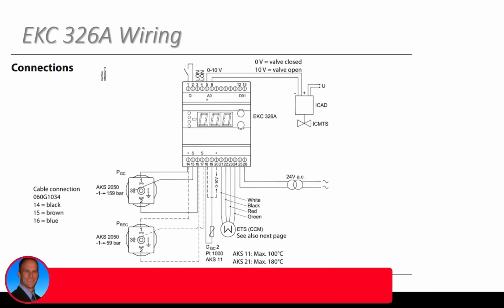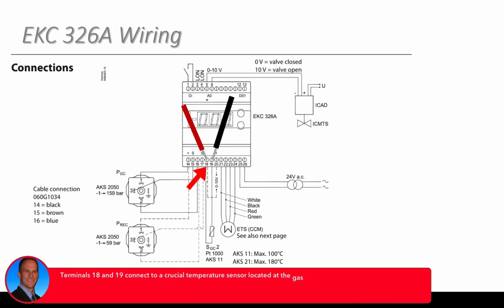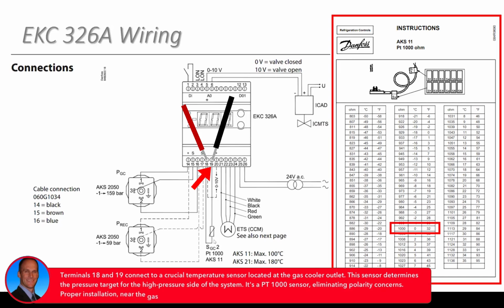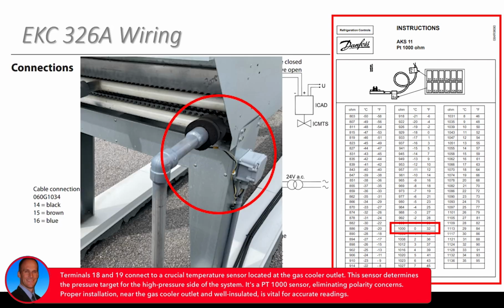Yeah, awesome. And then we've got terminals, we move on to 18 and 19 here. This is that very important temperature sensor we've got on the outlet of the gas cooler. And again, this sensor defines what pressure target we're going to have on the high pressure side of the system. So very important that we have that wired properly.